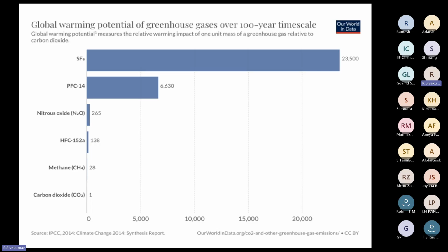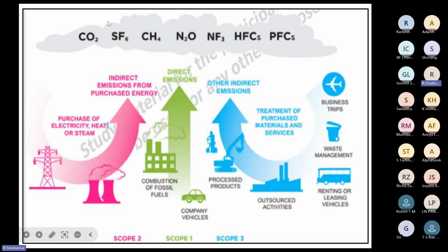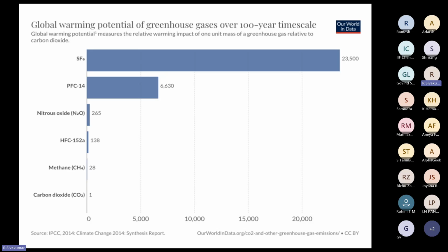So what is the impact factor? Most of the HT breakers we use in foundries and industry use SF6, sulfur hexafluoride, and it is listed among the greenhouse gases by global warming potential. CO2 is sustained in the atmosphere for 1 year, and that equivalent value is 1. Similarly, for 1 kg of methane emitted to the atmosphere, it is equivalent to 28 kg of CO2. That is compared with the base, CO2. Methane is 28 times higher than CO2. Similarly, HFC is 138 times, and SF6 is the very highest, 23,500. In arriving at the carbon footprint of an industry, these classifications are used to arrive at scope 1, scope 2, scope 3.